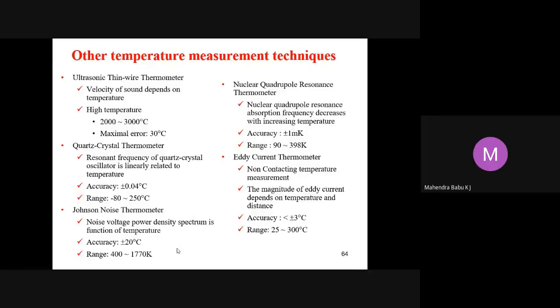Quartz crystal thermometer, where the resonant frequency of the quartz crystal oscillator is linearly related to temperature, accuracy plus or minus 0.04 degrees Celsius, range minus 80 degrees Celsius to 250 degrees Celsius. Johnson's noise thermometer, where the noise voltage power density spectrum is a function of temperature, accuracy plus or minus 20 degrees Celsius, range from 400 to 1770 Kelvin.